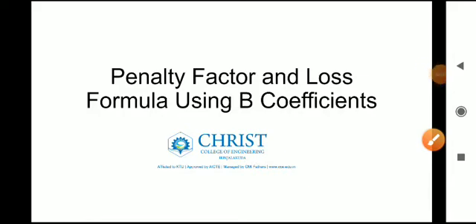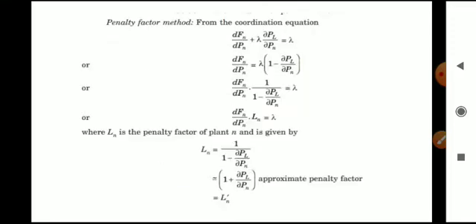Hi y'all, welcome to another video on the subject Power System Analysis. We are on Module 5, and today we are going to discuss the penalty factor and loss formula using B coefficients. The penalty factor can be derived from the coordination equations. The coordination equation is dFn/dPn plus lambda into ∂PL/∂Pn is equal to lambda, as we learned in the previous videos.